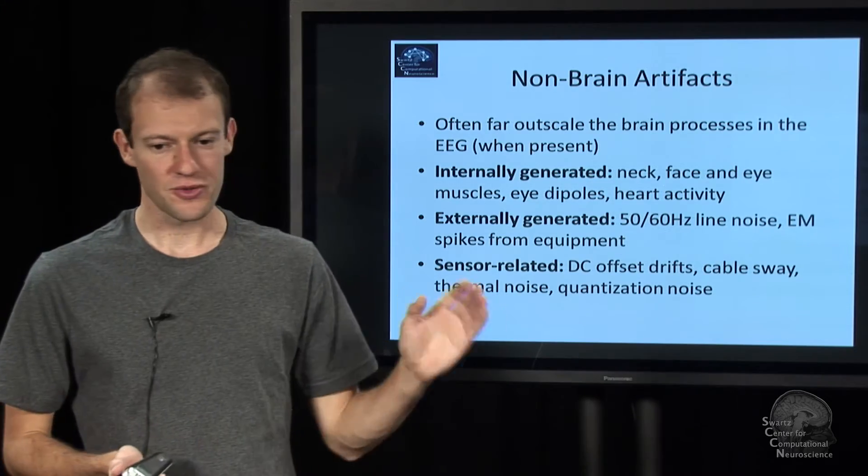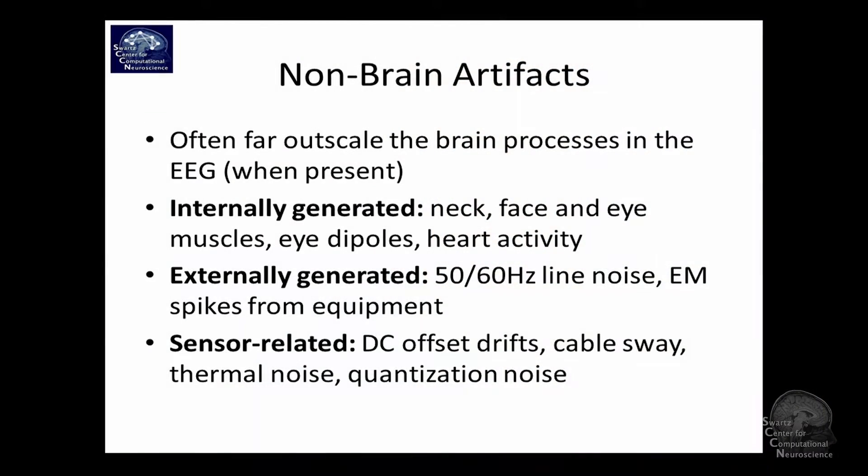There's also sensor artifacts: shifts in signal amplitude — called DC shifts or drifts — and cable sway artifacts, where if your cables are swaying around you get lots of low frequency shifts. There's thermal noise at the interface between the electrode material and the skin, which basically gives you the noise floor. It depends on the surface area of the electrode, the material properties, and things like that.